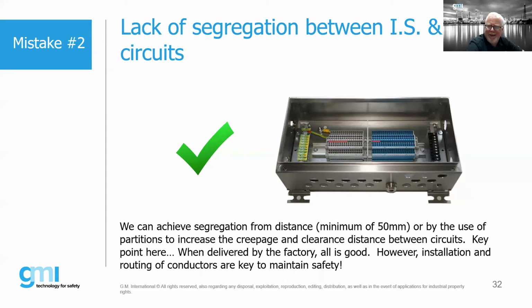One of the things that we cannot do is run IS and non-IS circuits within the same cable. We can run IS cables next to control cables, but we have to maintain either a 50 mil separation where we're running them in cable trays or cable ladders, or we have to make sure that one or both typically are armored or shielded or both. Now, everywhere in the world is slightly different with the requirements, but generally speaking, we all agree on a 50 mil separation. So realize it can be done in many different ways.